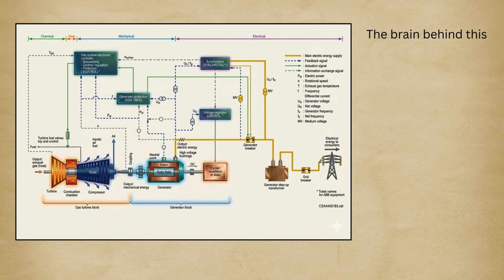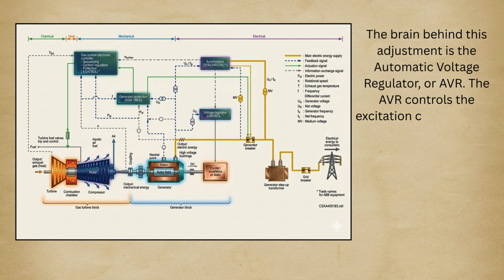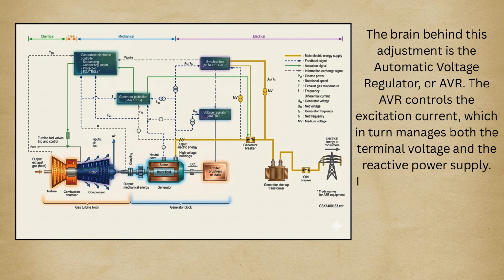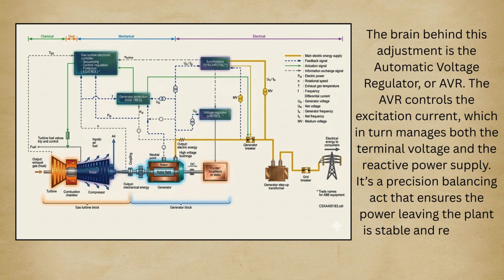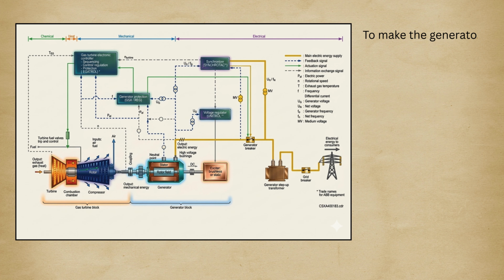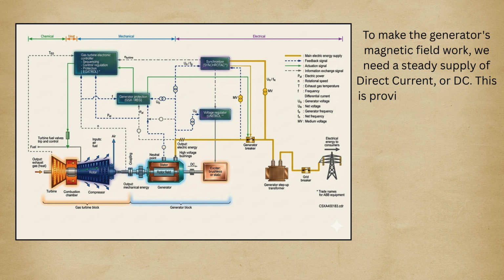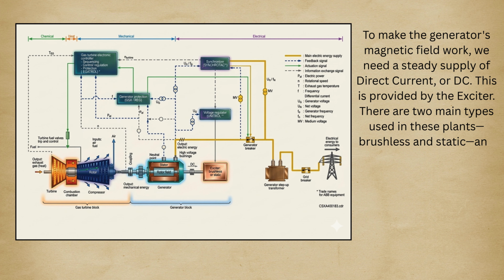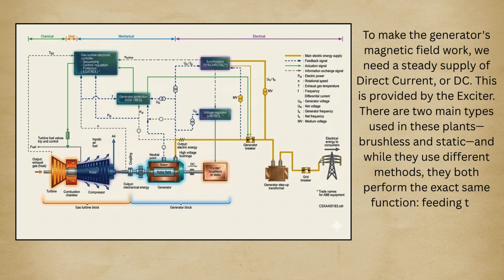The brain behind this adjustment is the automatic voltage regulator, or AVR. The AVR controls the excitation current, which in turn manages both the terminal voltage and the reactive power supply. It's a precision balancing act that ensures the power leaving the plant is stable and ready for the grid. To make the generator's magnetic field work, we need a steady supply of direct current, or DC. This is provided by the exciter. There are two main types used in these plants, brushless and static, and while they use different methods, they both perform the exact same function: feeding the energy that keeps the generator's magnetic field alive.